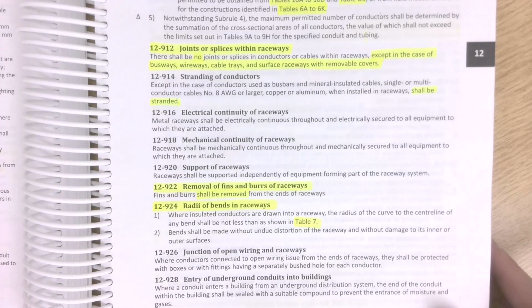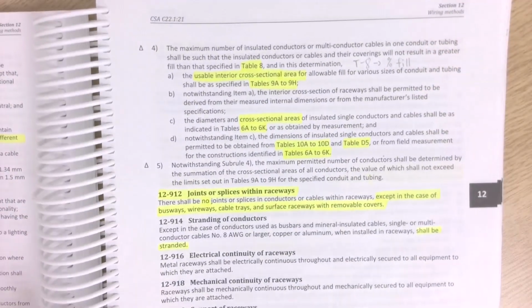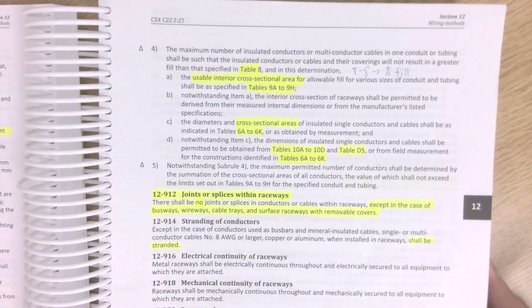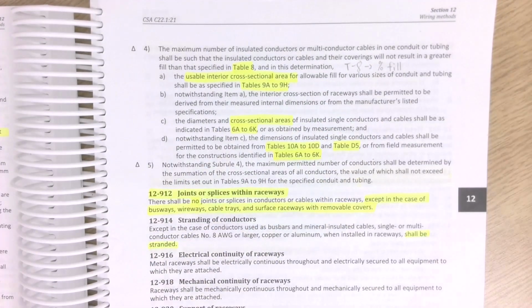A number 8 gauge that is solid that we do install, for example, would be the cable for your range. It is usually an 8-3, so it would be 8 gauge 3 conductor. And we talked about that in the branch circuits lecture. But the main one I want to look at today, the thing that most people seem to struggle with, is conduit sizing or conduit fill, or how many wires in a pipe, is another way to phrase it.